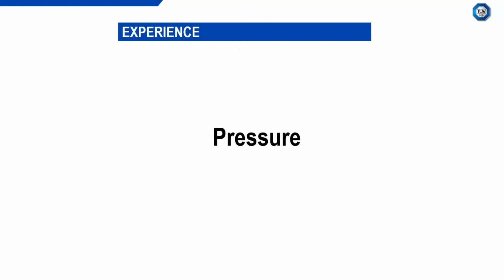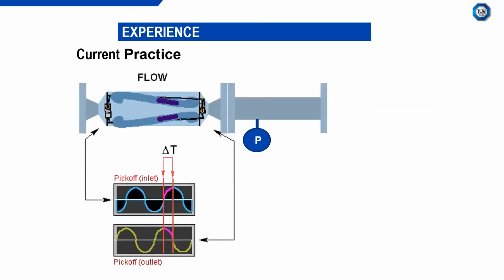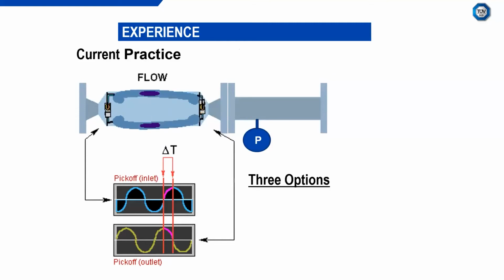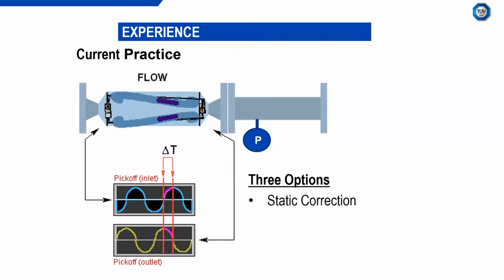So I'm now going to discuss with you some of the experiences we have with operating at elevated pressures with Coriolis meters. I have an animation here of a Coriolis meter, obviously with the exaggerated shift, the Coriolis twist that you can see here. It's maybe not quite as prominent as that. We have an inlet and outlet pick-off. As mass flow goes by, it causes a shift in the Coriolis tubes from the inlet to the outlet. You get a delta T from the two pick-offs. This delta T is proportional to the mass flow.